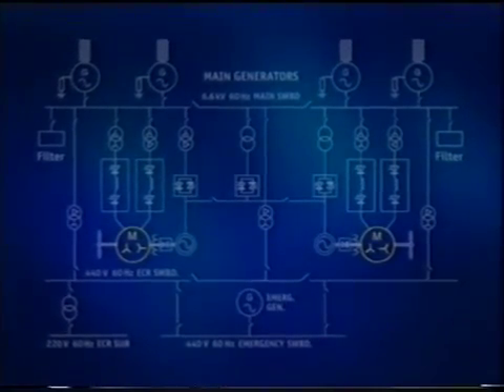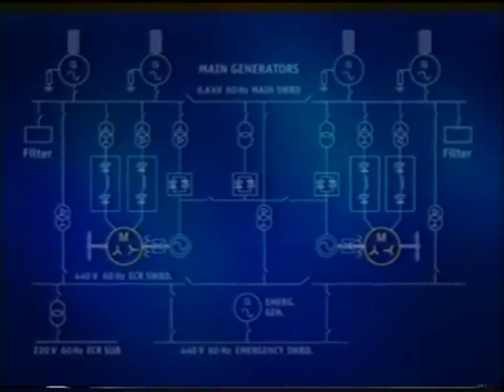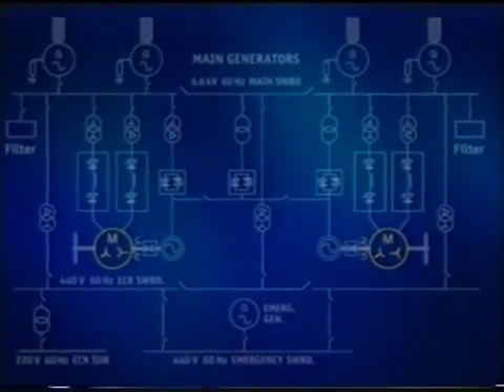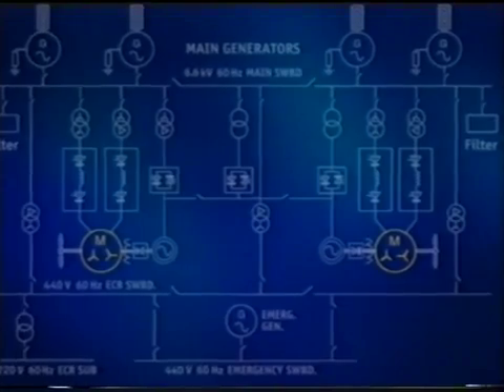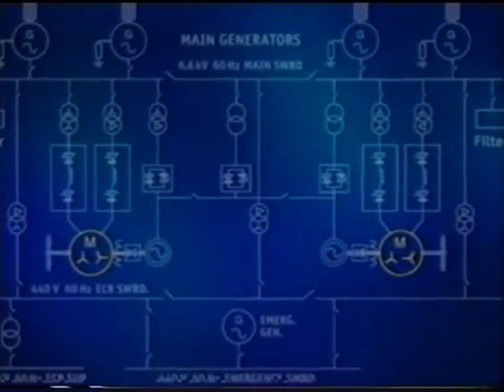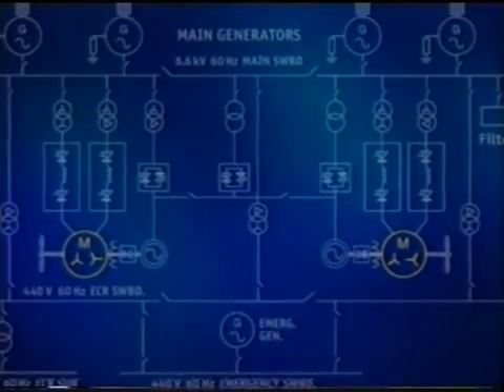The propulsion motors have 2 separate 3-phase stator windings fitted 30 degrees apart. This arrangement creates a 12-pulse torque to reduce shaft vibration. In an emergency, it would be possible to run as a half motor with reduced power output, but the 6-pulse operation will increase vibration and voltage harmonic disturbance. Each half motor is fed from a separate converter.